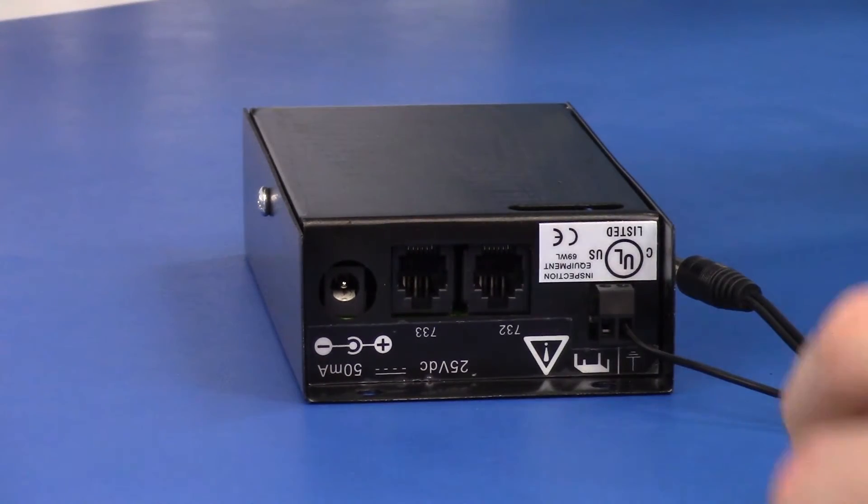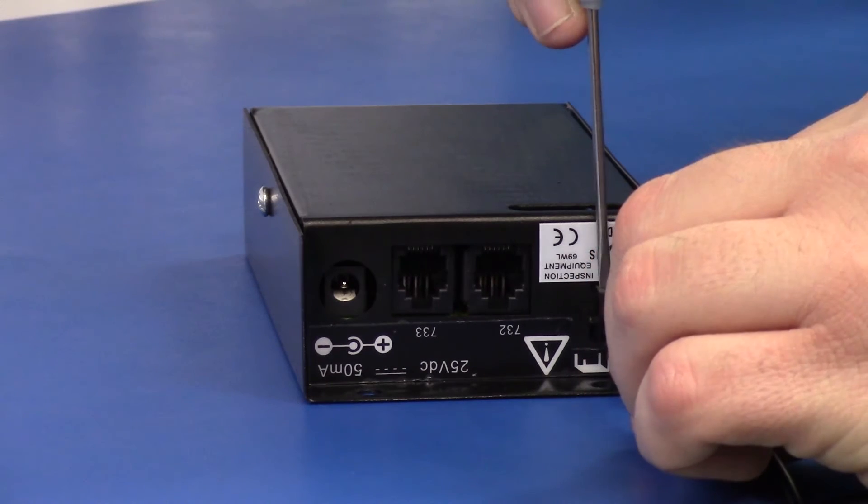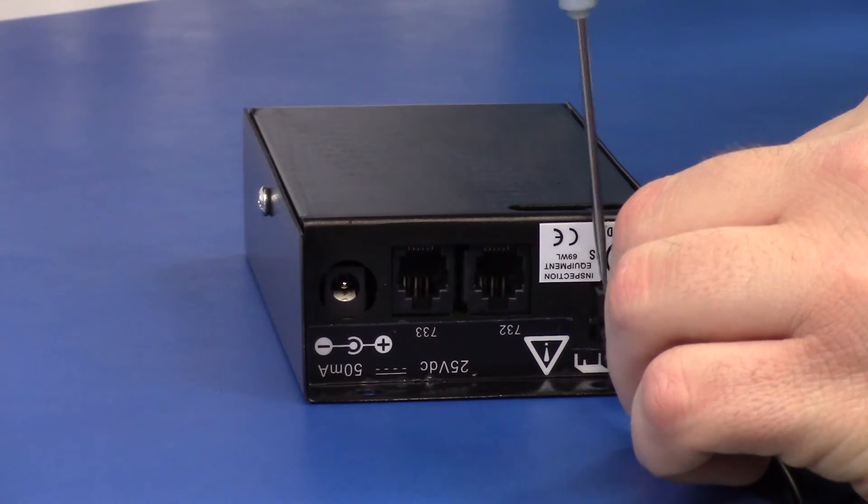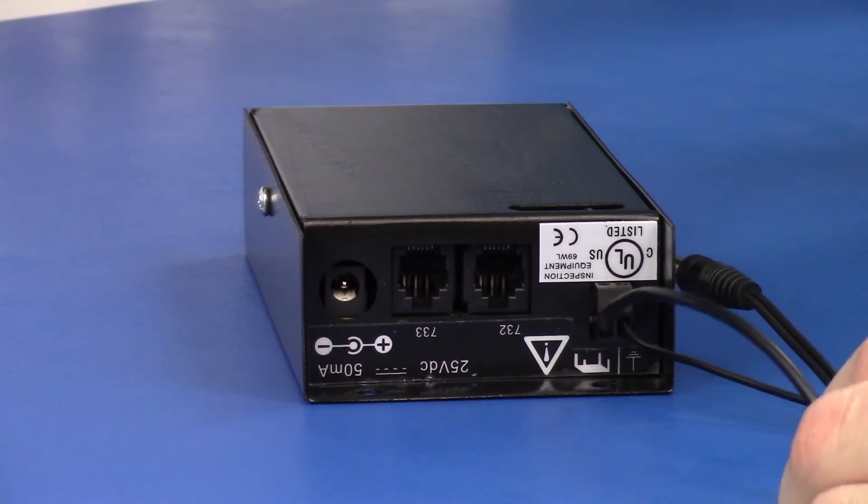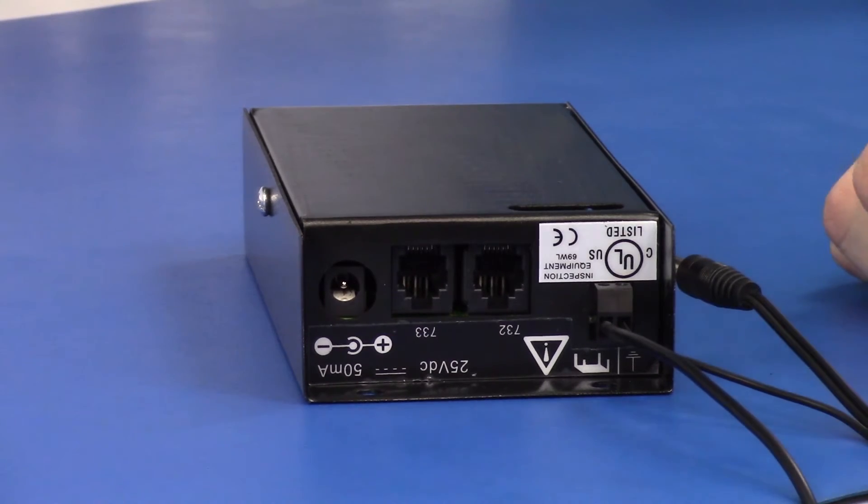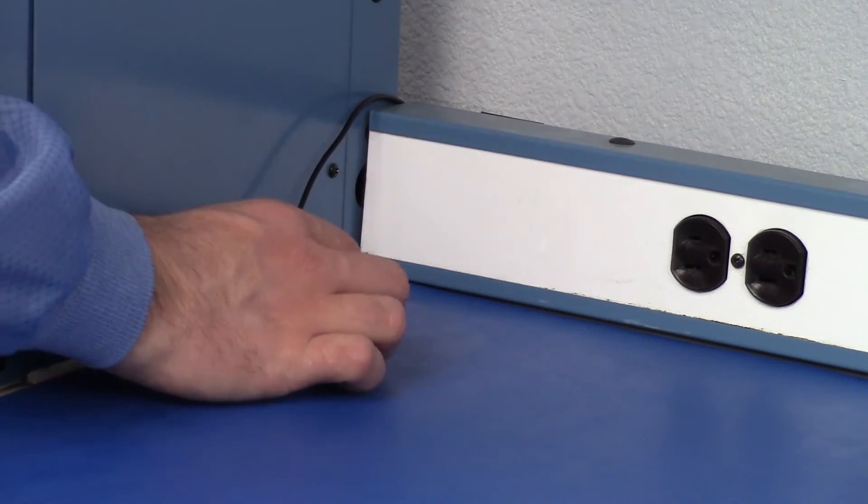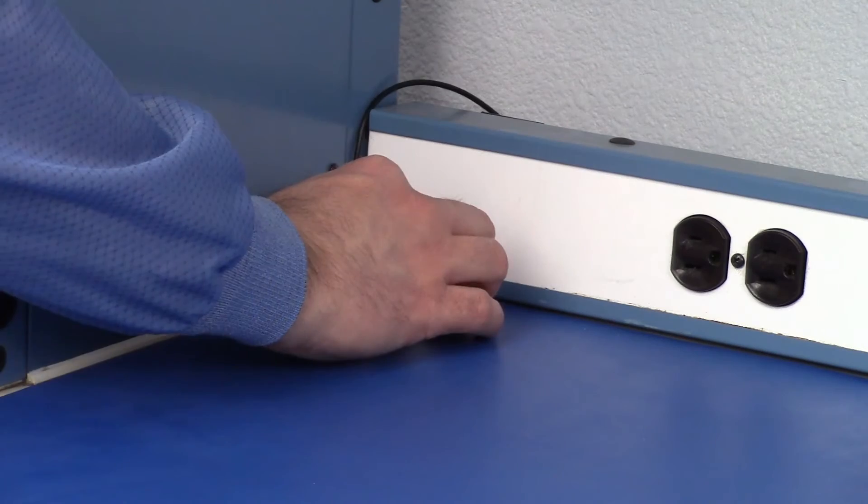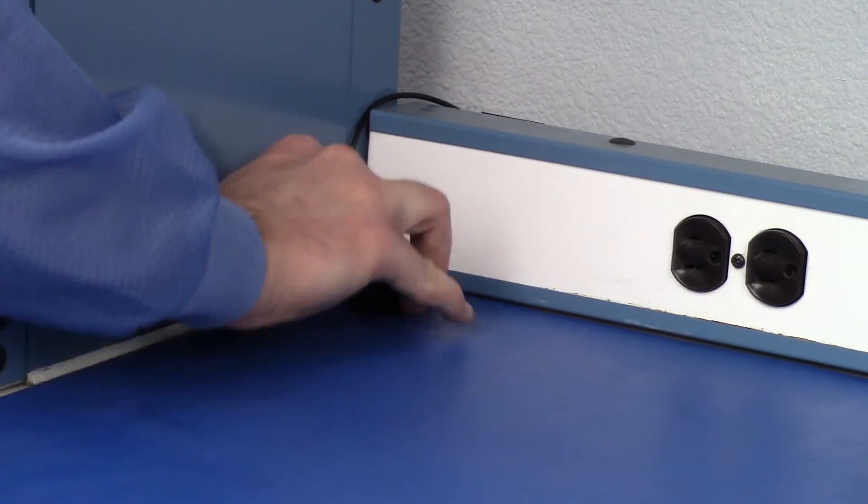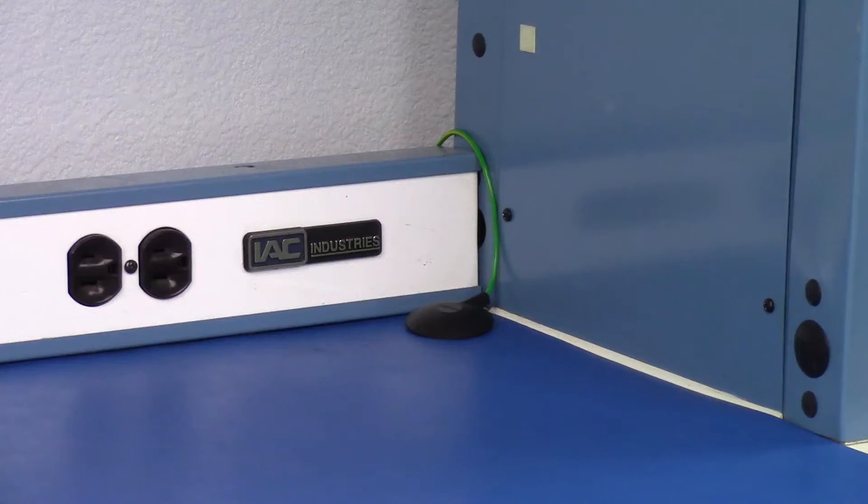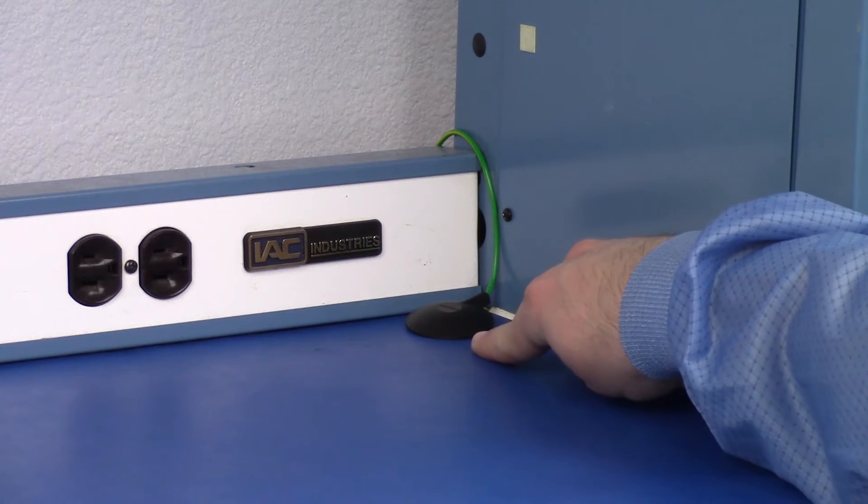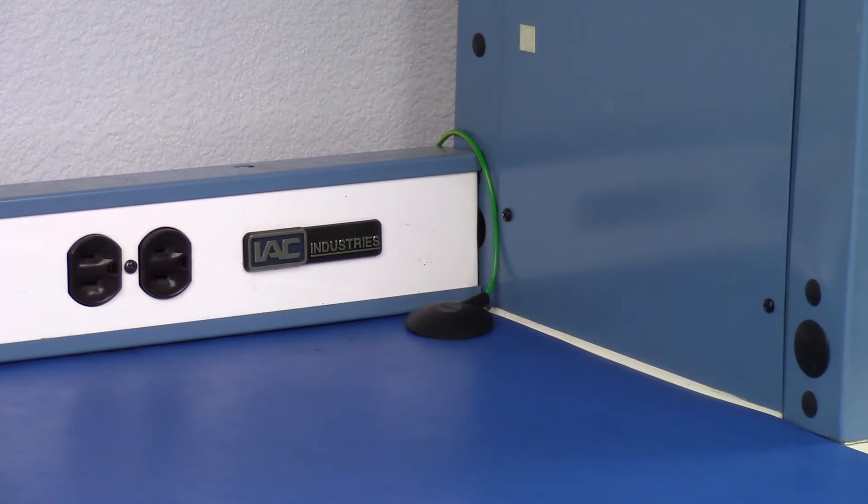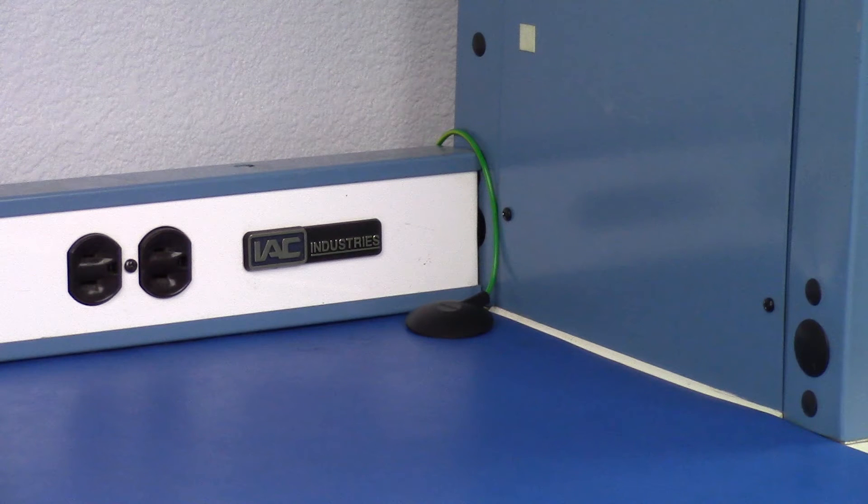Use the same method to connect the mat monitor cord to the mat terminal on the two-wire terminal block. Connect the opposite end of the mat monitor cord to a grounded work surface mat. It is important to note that the SES724 Workstation Monitor only monitors the mat's connection to ground. It does not ground the mat. The mat must be grounded separately.